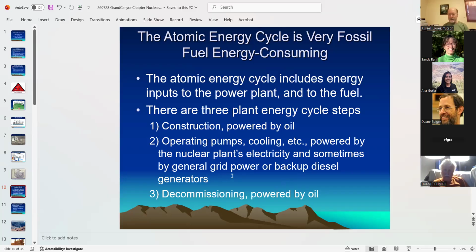Another example: when Palo Verde goes down for fueling, an unforeseen accident, or maintenance issue, it has to be started by another power plant. Two of those plants are at the plant in Tucson. They're called black start plants, and they're specifically calibrated to most efficiently start Palo Verde up. Those are gas plants.